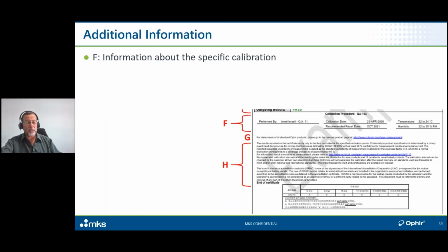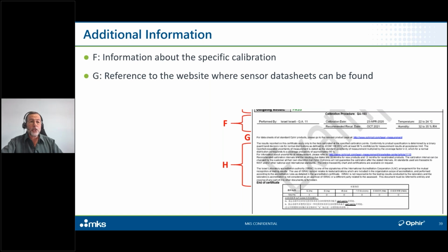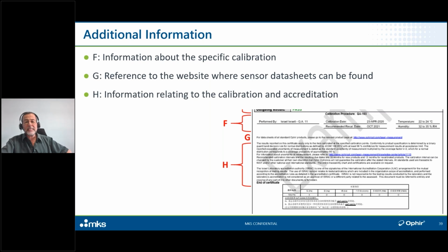Okay, F, information about the specific calibration. Reference to the internal procedure number that we used, again, so that everything is traceable, who performed it, the date, the environmental conditions, the temperature in the lab, the humidity in the lab, and so on. G, reference to the website where all the data sheets can be found. And H, this is the bit with a whole lot of text that probably only the QA professionals would be interested in reading. This is information relating to the calibration, the accreditation, particularly the decision rule that's used to determine pass-fail, and so on.